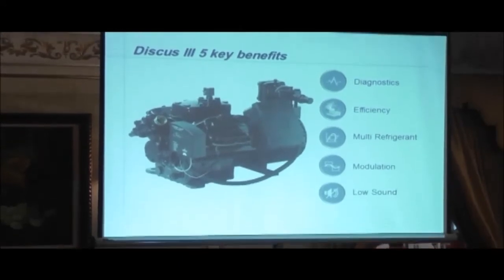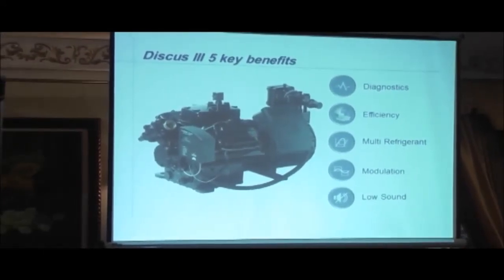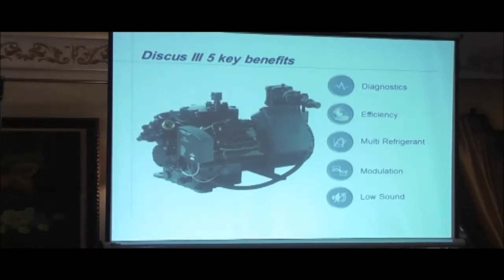So why did we do this? Well, at the very top of our list, we always try and improve efficiency. We improve reliability, and by achieving or trying to achieve that, we are now introducing diagnostics, which is basically an electronic platform to help diagnose and solve issues with the compressor and your system. The new compressors are also multi-refrigerant. Okay? We try and design the compressor so that you can use it with R22, 134A, 404A, etc., depending on the application.